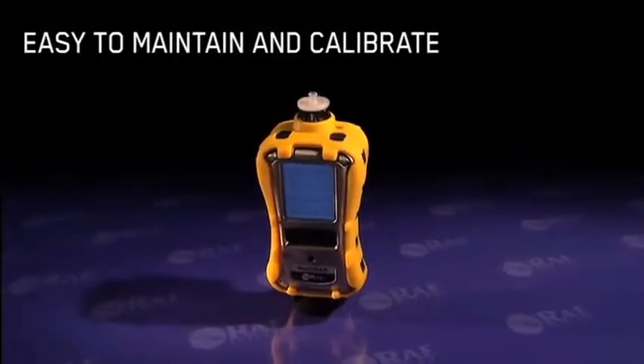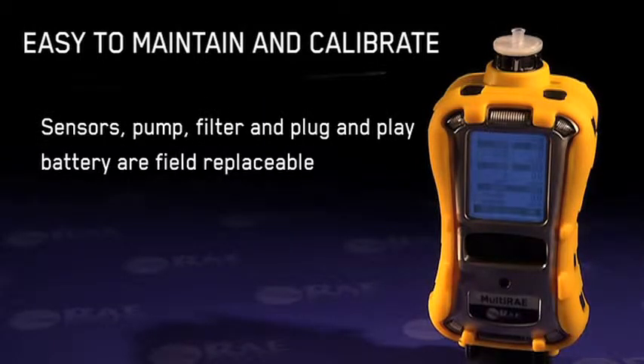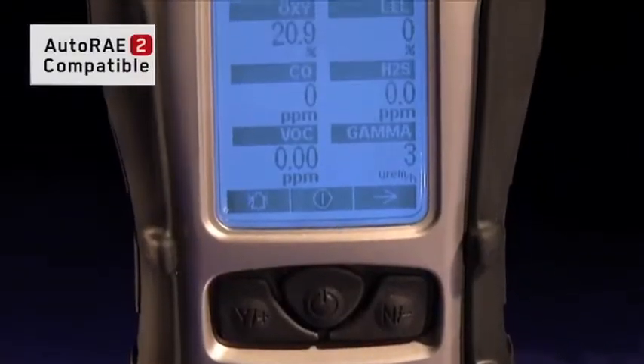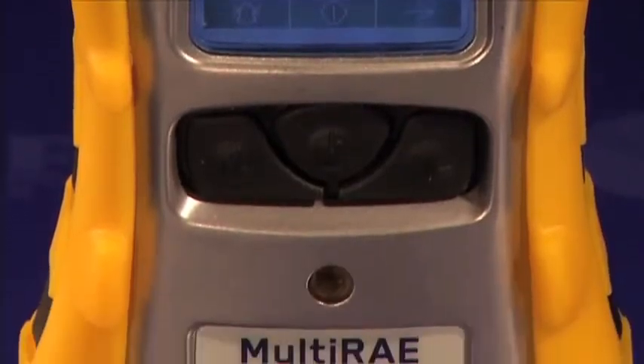The MultiRAE instruments are designed for simple and efficient maintenance and calibration. Their sensors, pump, filter, and plug-and-play battery are field replaceable, while the AutoRAE 2 automated test and calibration system makes bump testing and calibration as easy as a press of a button.